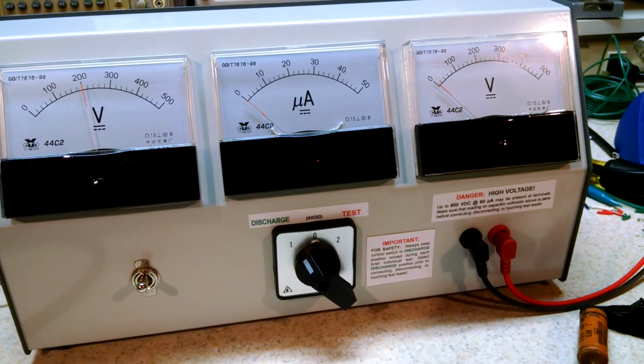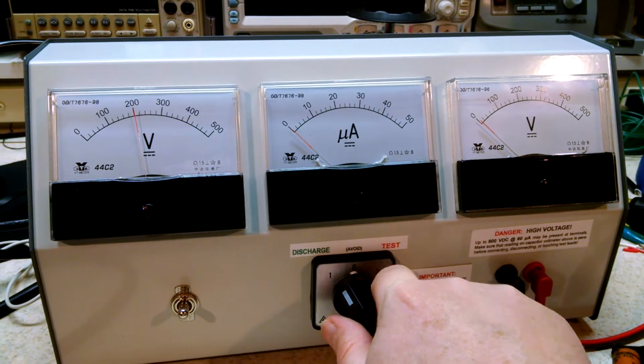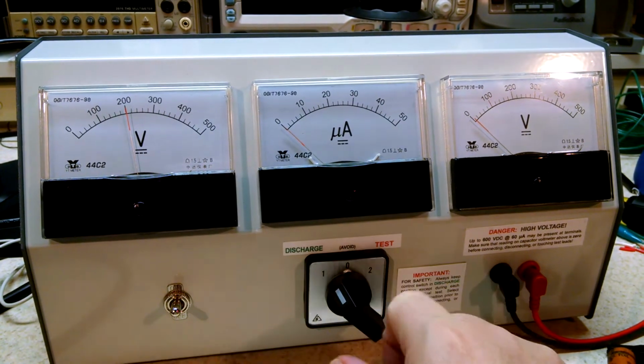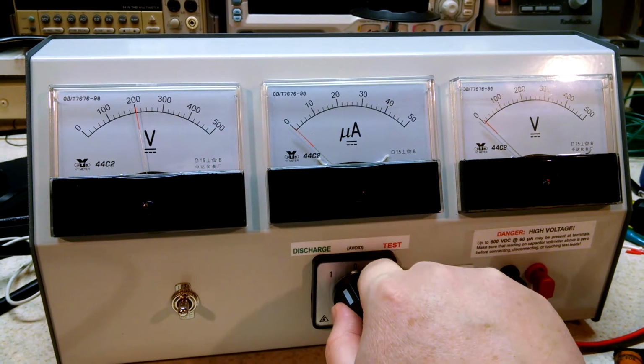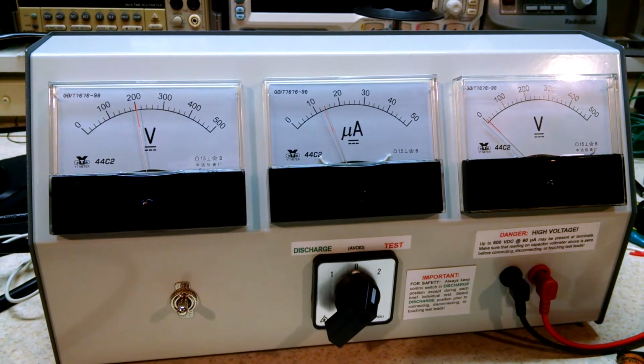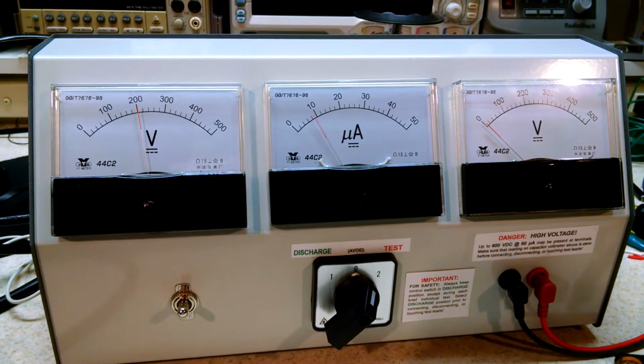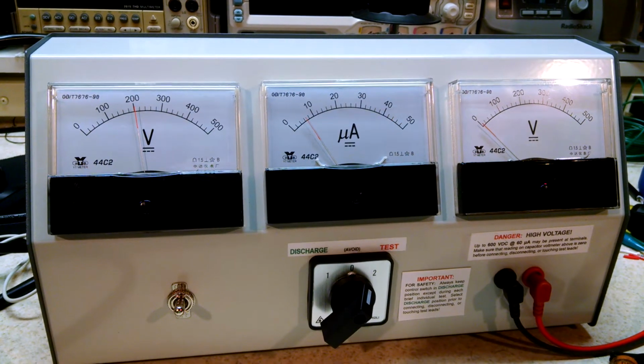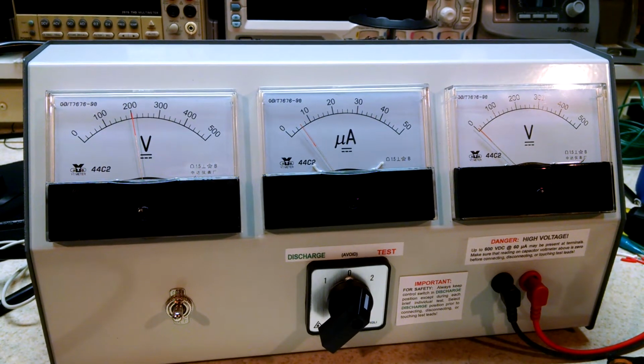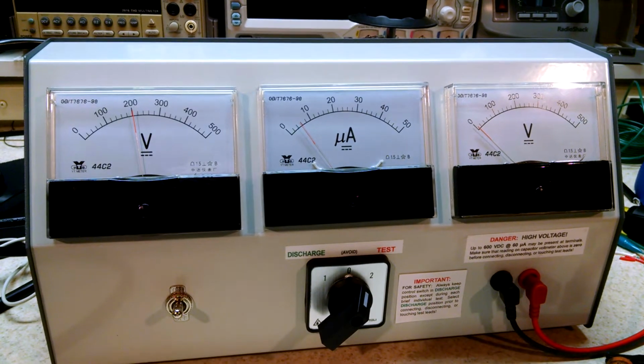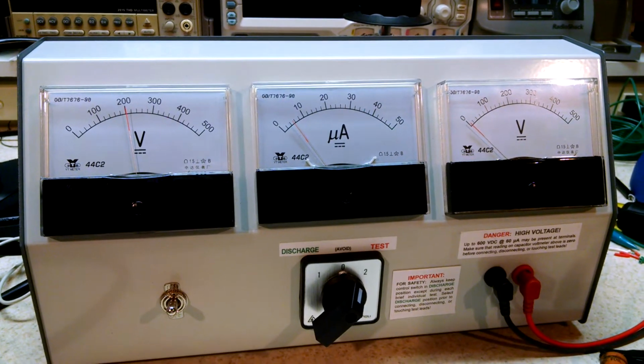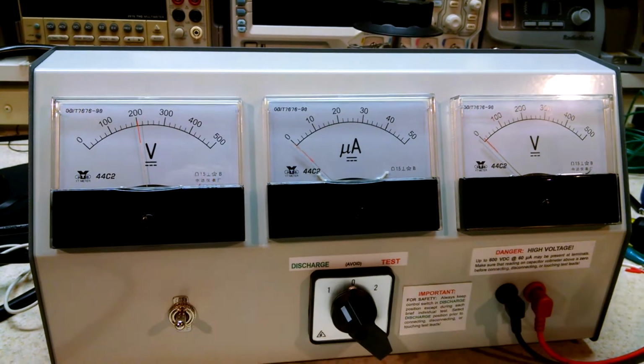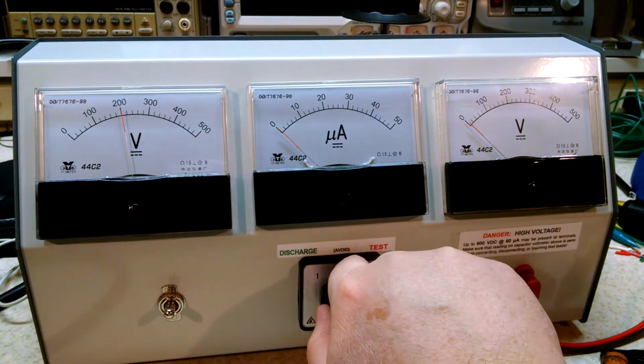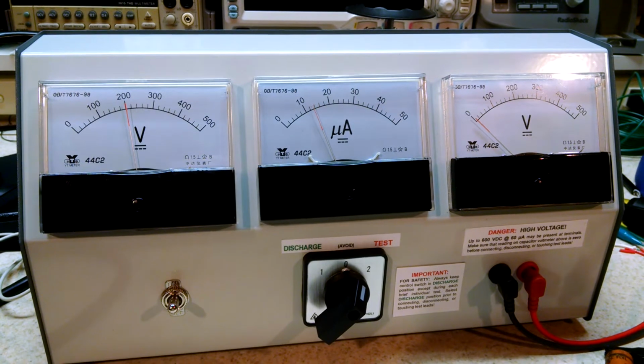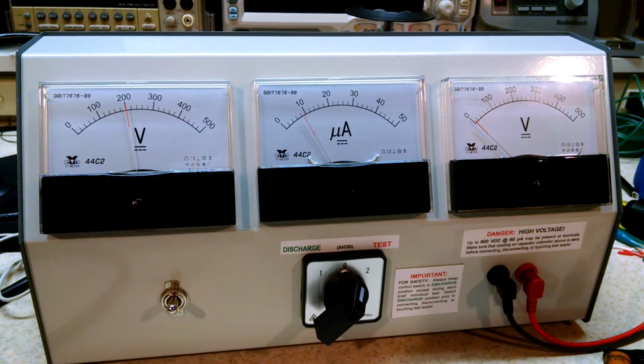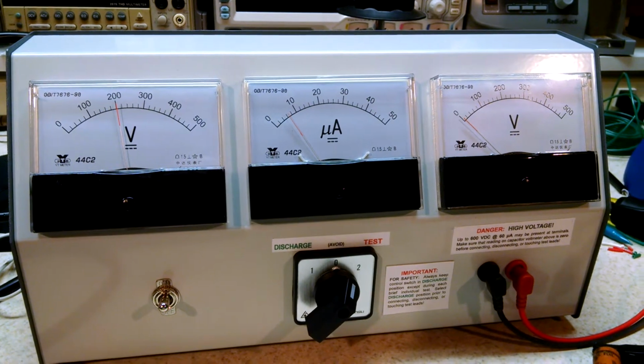I'll move the capacitor a little bit further away from my hand here, and now when I switch to the test position, we will see this meter rise and then fall a little bit. So it has fallen, but it's not returning all the way to zero. I can repeat the test, go to the discharge position. So this is exhibiting some leakage current.